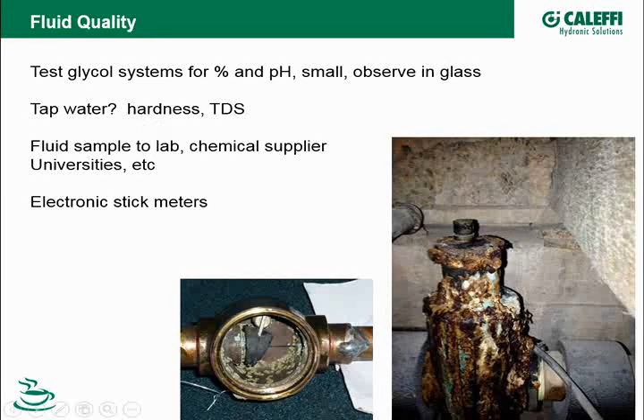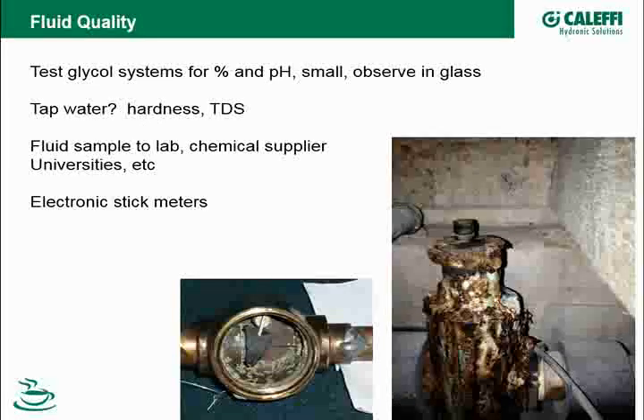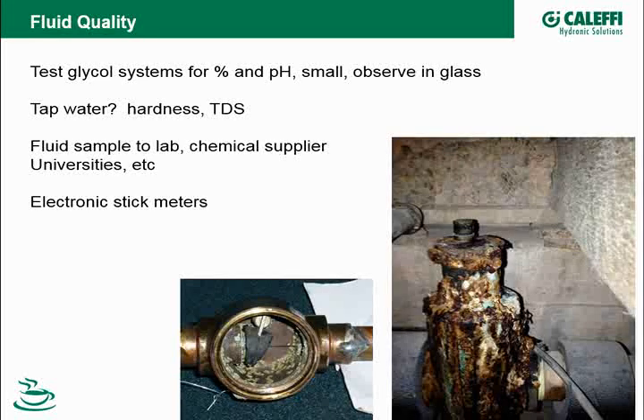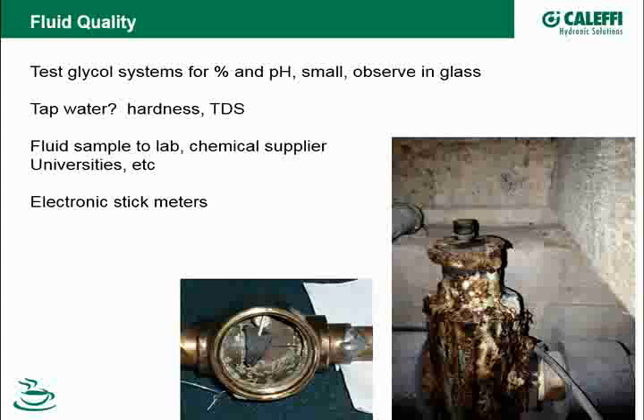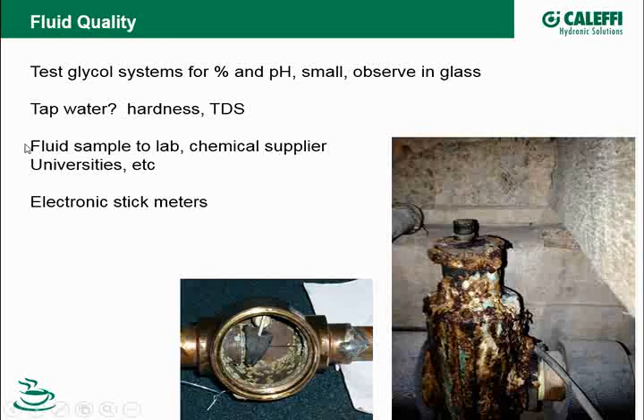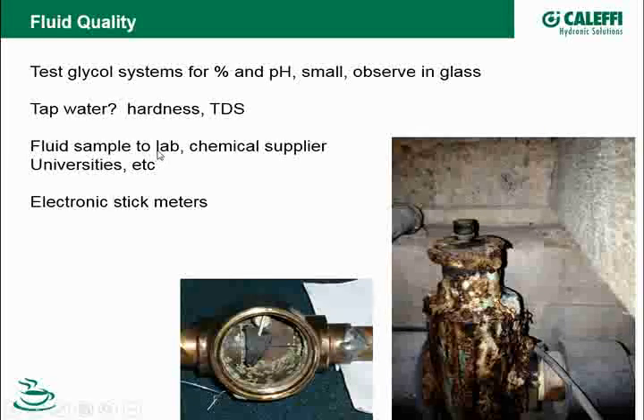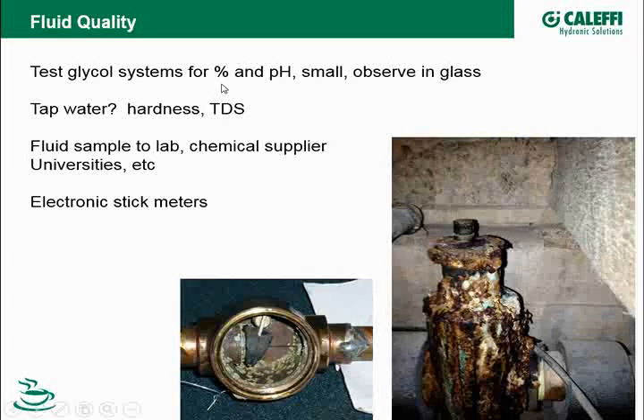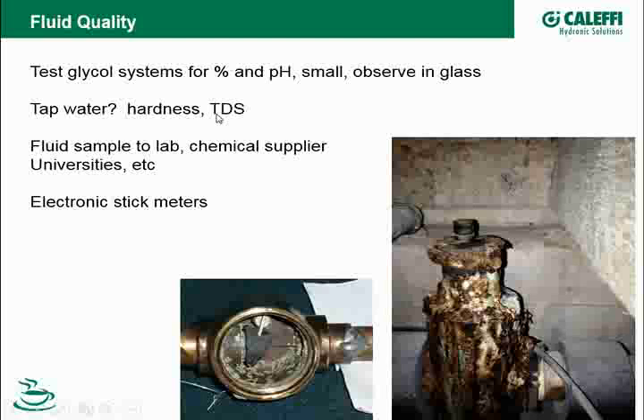I'll pull some of the installation information from various different boiler manufacturers to see what they're saying about the water quality, because they can refuse a warranty if you have an issue with equipment and that water wasn't maintained or put in with the right spec on it. Now, if you have a problem job where you're having issues with that, you can send a lab a sample of the water, and they can do a more thorough analysis than you can do with some of these little stick meters that I'm going to show you coming up.